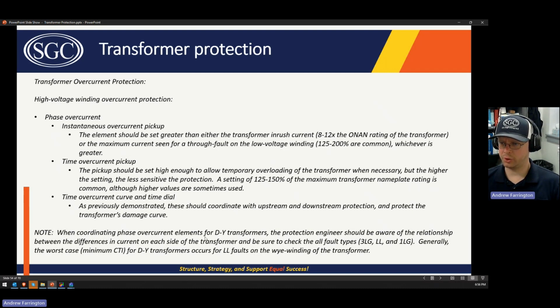And then a note for when you're doing coordination between delta Y transformers, I don't remember if I touched on this or not, but for phase faults for delta Y transformers, the worst case coordination time interval is going to be for phase-to-phase faults. The reason is, if you have a phase-to-phase fault on the low side, the Y winding side of the transformer, when you reflect those currents up through the transformer to the delta side, there's going to be one phase that is tied to both of the faulted phases on the low side. Say it's a B to C fault, there's going to be one winding, either the B or the C winding, depending if it's a DAB or DAC transformer, that's going to see the fault current for both of those. And so it'll be the square root of 3 higher than the other two phases. So that phase will see current that would be the same if you had a 3-phase fault.